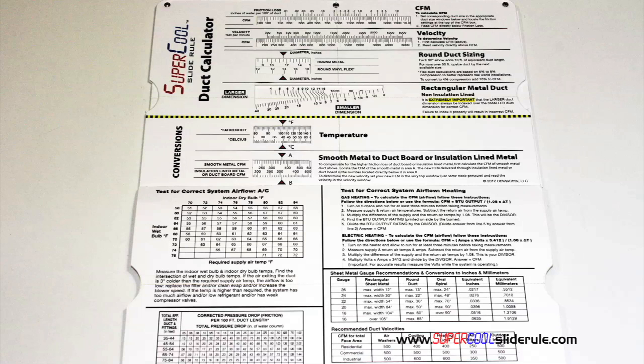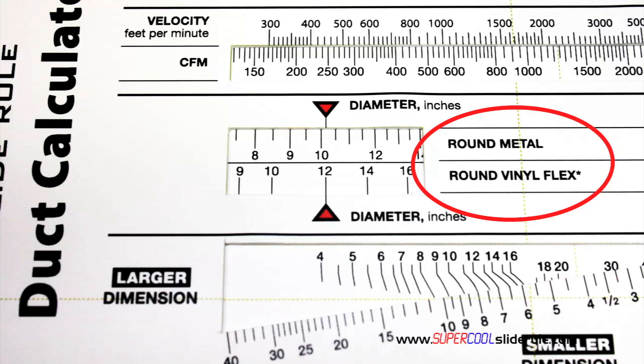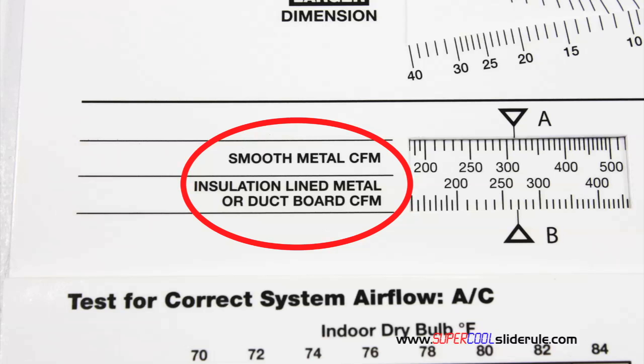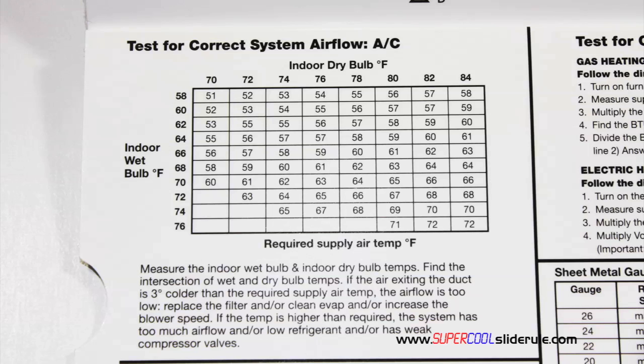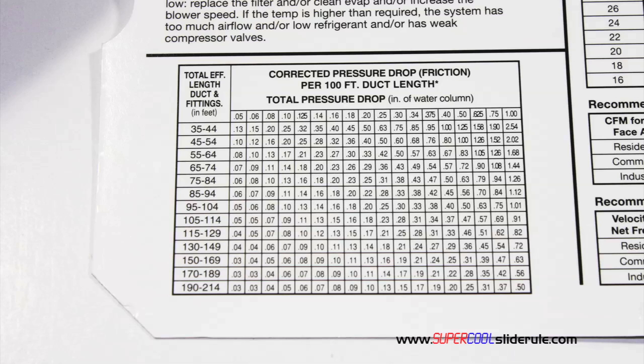Inside is packed with even more information. It performs sizing of both metal and flexible duct. It has the only direct reading conversion from smooth metal to insulation-lined metal we've ever seen. The majority of technicians have never been taught that if the insulation is on the inside of the ductwork, you cannot size it with a regular duct calculator. It also has step-by-step directions for determining airflow through a gas furnace, electric furnace, or an air conditioning unit, plus pressure drop multipliers for ductwork as well as recommended velocities.